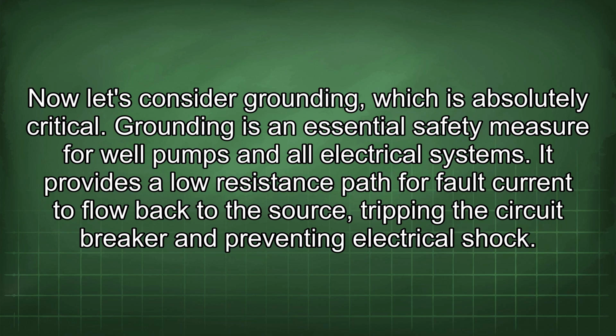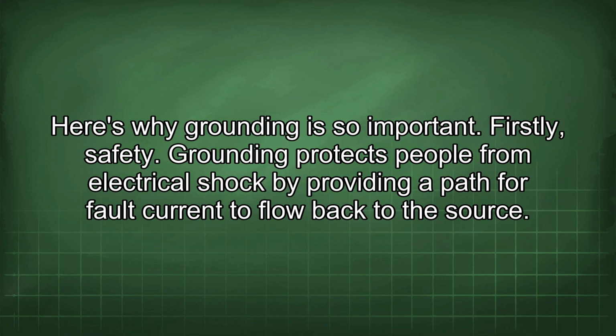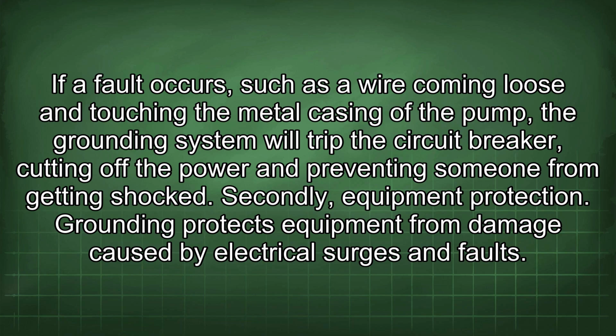It provides a low resistance path for fault current to flow back to the source, tripping the circuit breaker and preventing electrical shock. Here's why grounding is so important. Firstly, safety. Grounding protects people from electrical shock by providing a path for fault current to flow back to the source. If a fault occurs, such as a wire coming loose and touching the metal casing of the pump, the grounding system will trip the circuit breaker, cutting off the power and preventing someone from getting shocked.